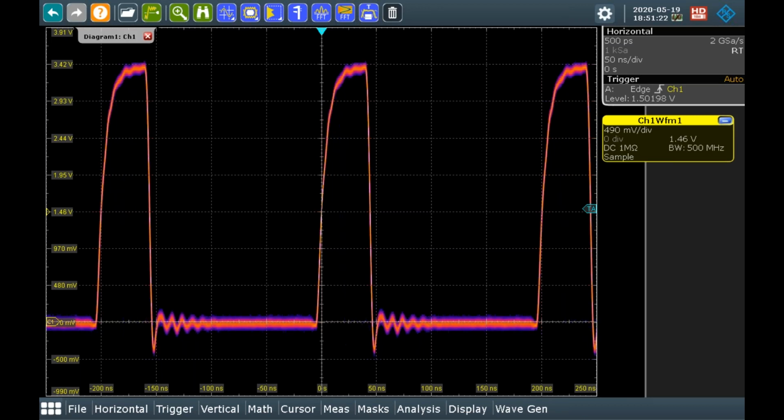So a little bit long-winded there, but we do view analog scopes as very reactive, and now I think the digital scopes have caught up and they're able to have that same sort of response, but also allow you to post-process the data and save it off and save and recall settings and all the good things that we love about digital scopes.